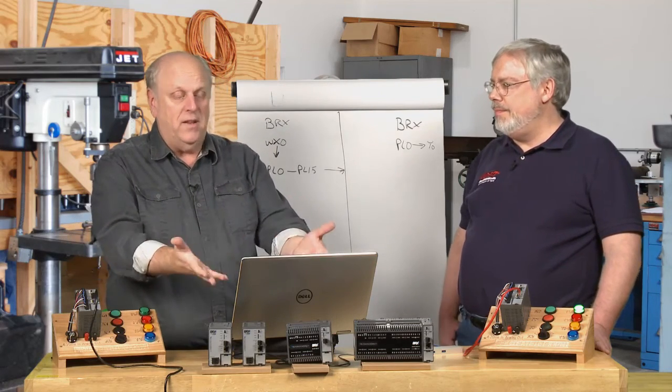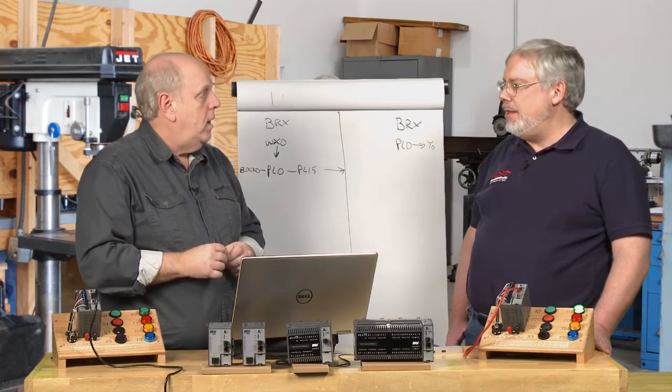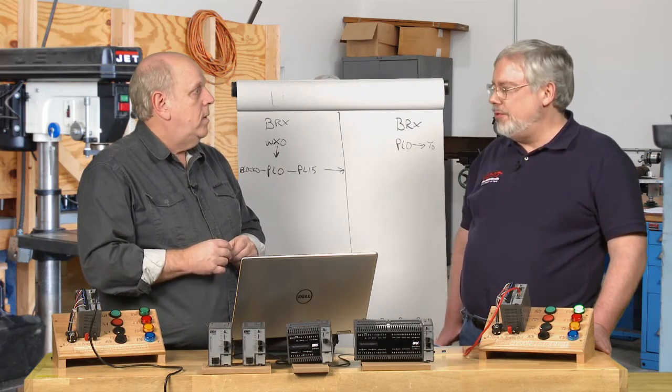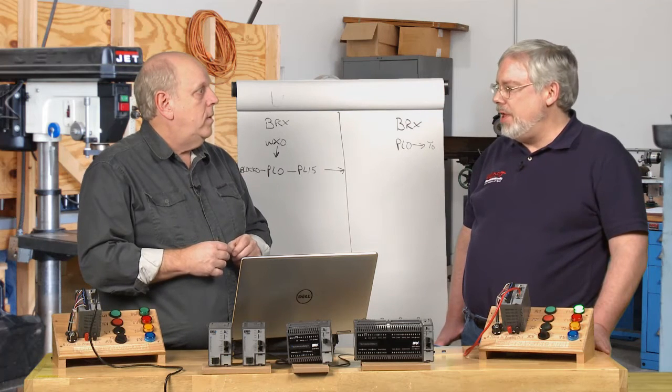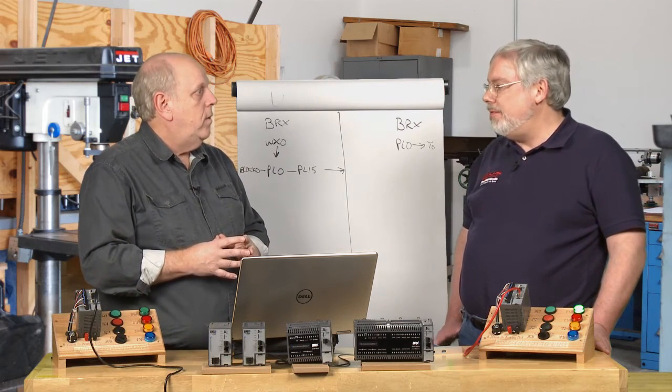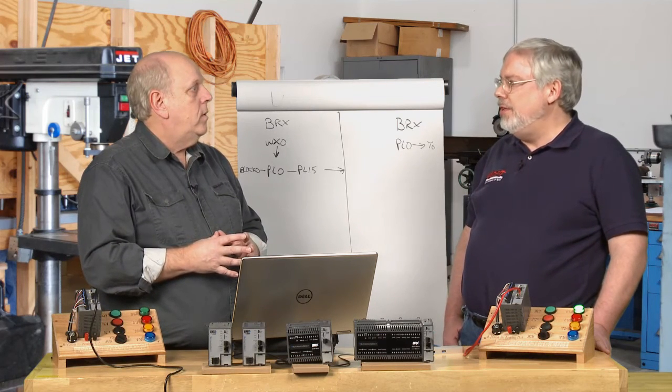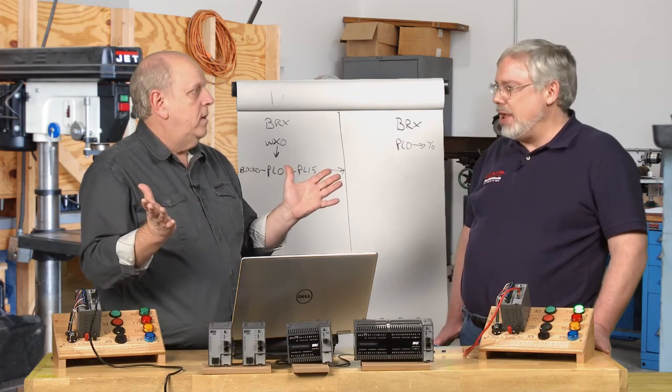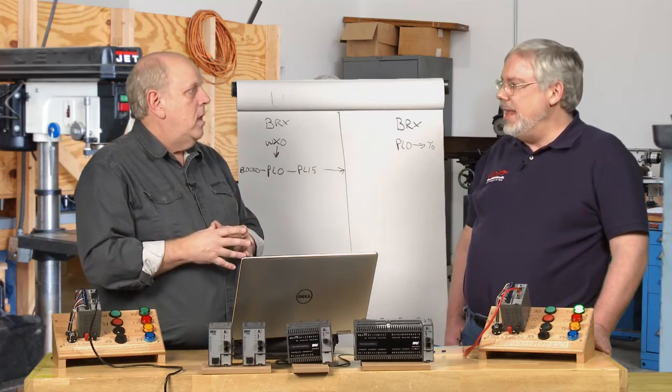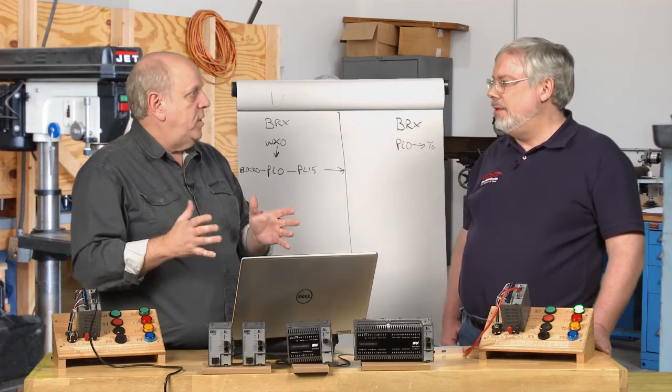There's no configuration because it's ethernet. The PeerLink protocol automatically works. Any Do-more PLC that has a PeerLink instruction can either publish one of 16 blocks, but you could have a thousand Do-more PLCs subscribing, listening, and getting all those 16 blocks. Now, all of them do that except the BRX that don't have built-in ethernet.